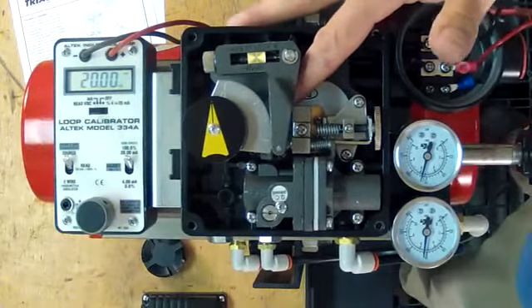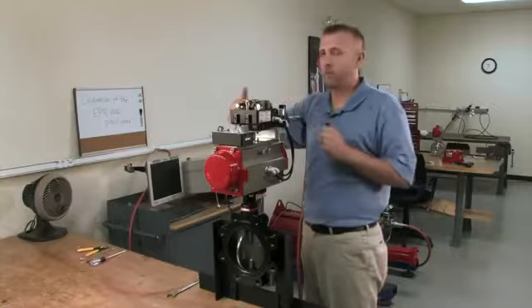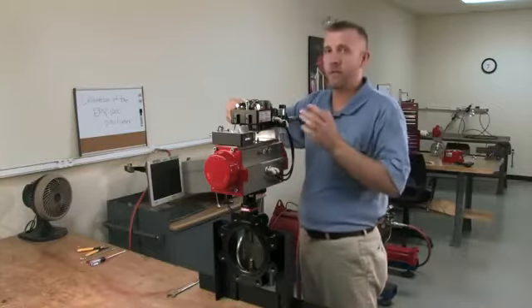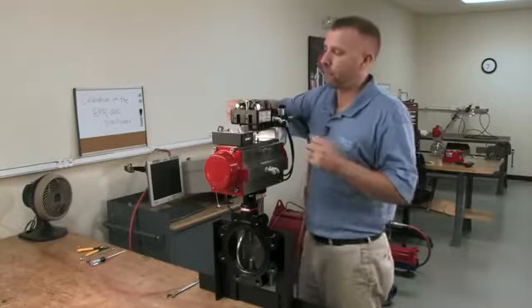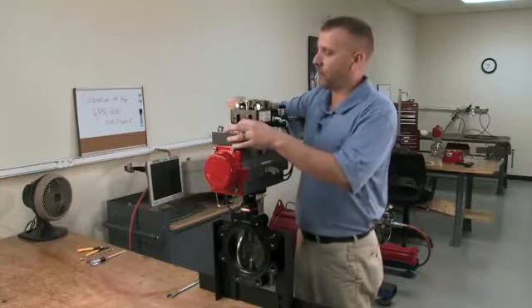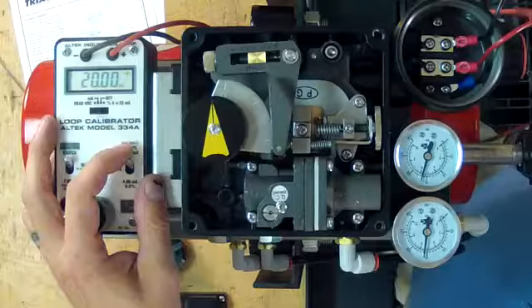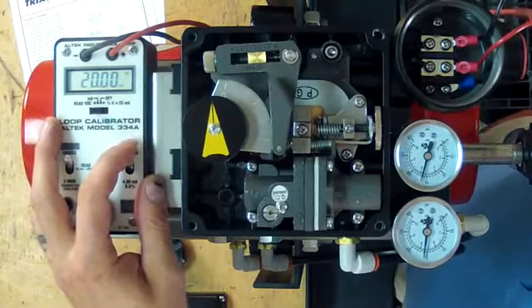Check with the counterweight, pull towards you. And no air has bled off on the actuator. That means you are in a full open position. Now we're going to check our mid one more time by going to 4 milliamps, then 12.